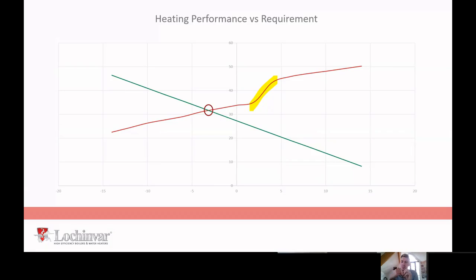But it's not that cold outside that there's not much humidity. So a quite humid atmosphere, going over an evaporator grill, starts to form an ice layer on the heat pump. And when you get that ice layer, even though the fans are spinning, drawing air from outside across our evaporator to take in that ambient heat, those ice deposits restrict the airflow. And when they restrict the airflow, they affect its performance. When they affect its performance too much, it will go into a defrost function to get the frost off the evaporator so it can start operating efficiently again. So that's why between 4 and 2 degrees, we get this sudden drop off in performance.